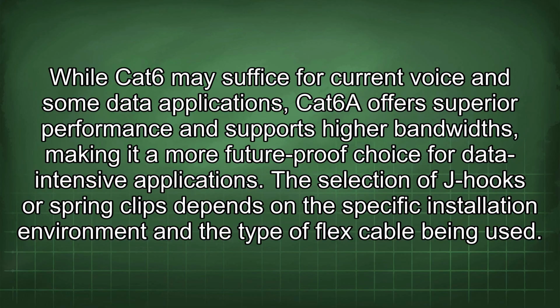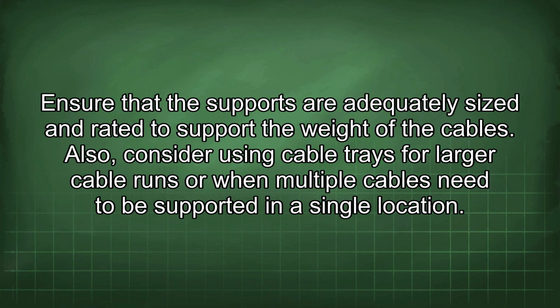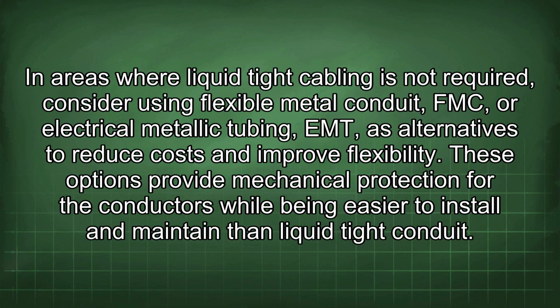The selection of J-hooks or spring clips depends on the specific installation environment and the type of flex cable being used. Ensure that the supports are adequately sized and rated to support the weight of the cables. Also, consider using cable trays for larger cable runs or when multiple cables need to be supported in a single location. In areas where liquid-tight cabling is not required, consider using flexible metal conduit (FMC) or electrical metallic tubing (EMT) as alternatives to reduce costs and improve flexibility. These options provide mechanical protection for the conductors while being easier to install and maintain than liquid-tight conduit.